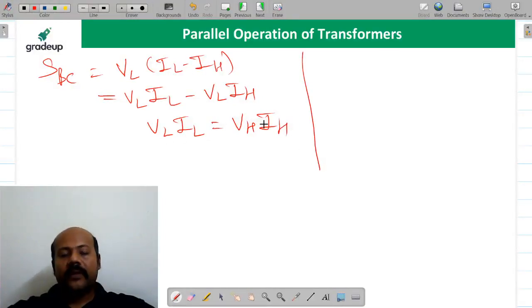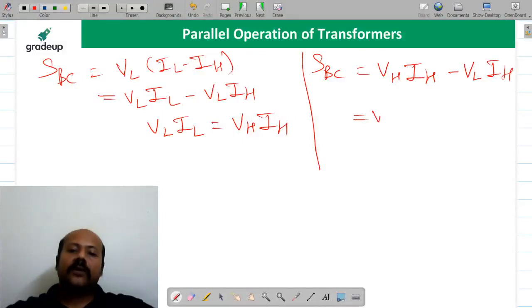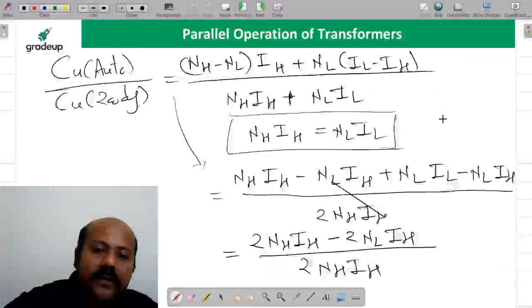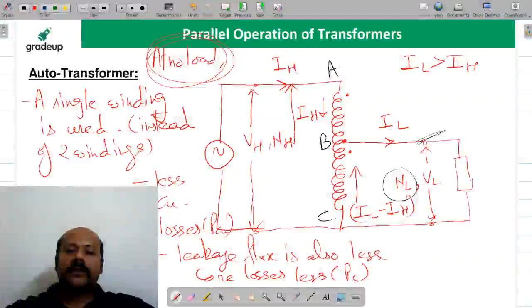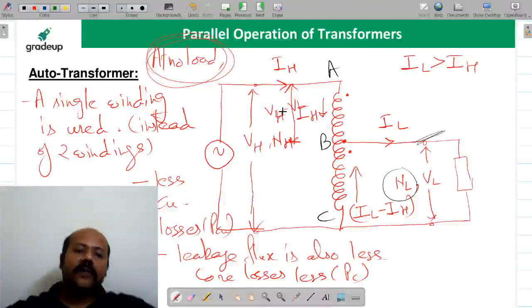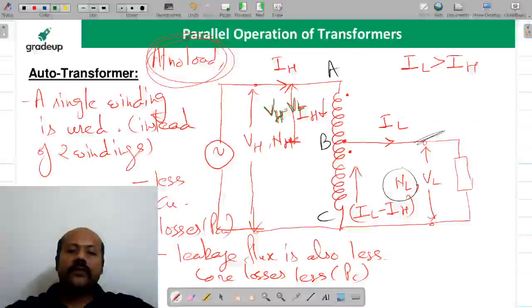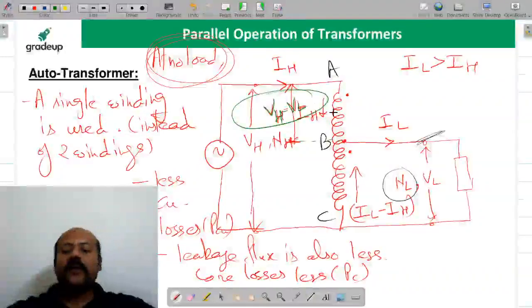This we have seen for the common flux or the voltage per turn induced in the autotransformer, equation number 1. So you can write this power for the BC part of the winding as VH IH minus VL IH, or as VH minus VL multiplied by IH, which is common. Now can you tell me what is VH minus VL multiplied by IH? This VH minus VL is for the AB part of the winding, the AB section.